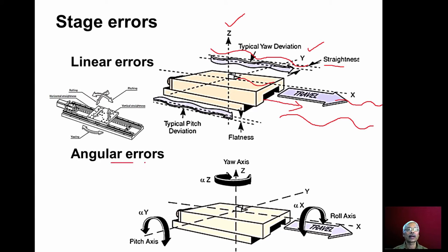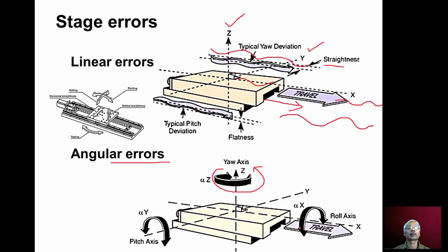Coming to the angular errors in each axis, there can be yaw error — the table rotating in this fashion. Similarly, along the pitch axis the table surface may tilt, and along the x-axis the table surface may roll. So apart from linear errors in x, y, z direction, there can be roll axis error, yaw axis error, and pitch axis error.